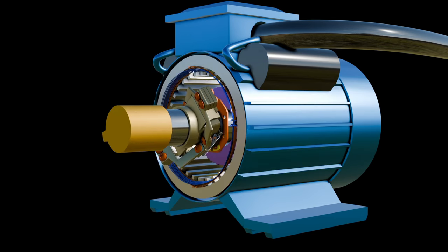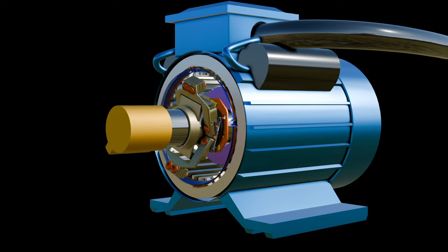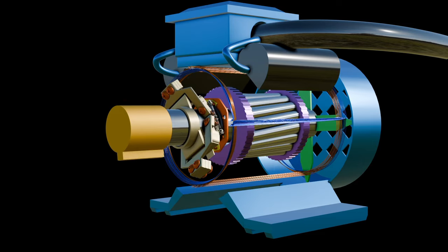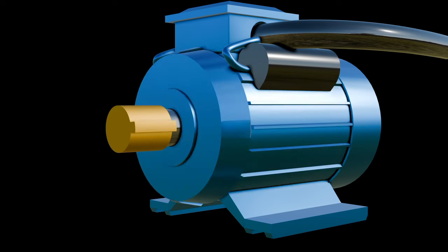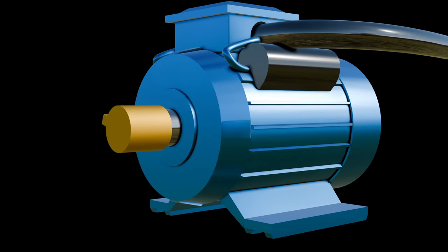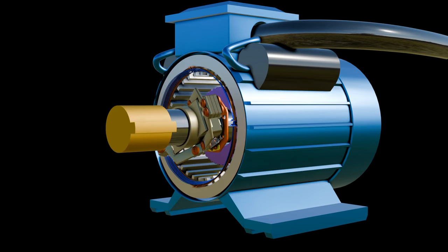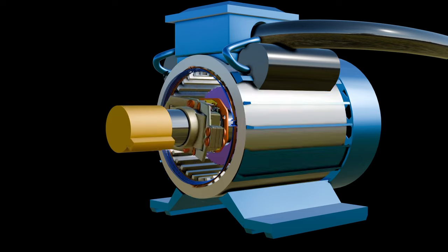So starting torque of this motor is very high compared to the split phase induction motor. This starting torque is 300% more than the full load torque. Due to high starting torque, this motor is used in the applications where high starting torque is required like a lathe machine, compressors, drilling machines, and the rest.